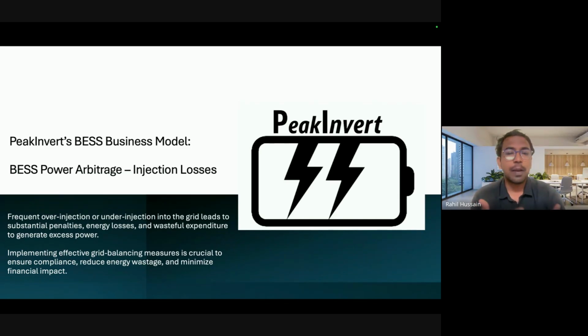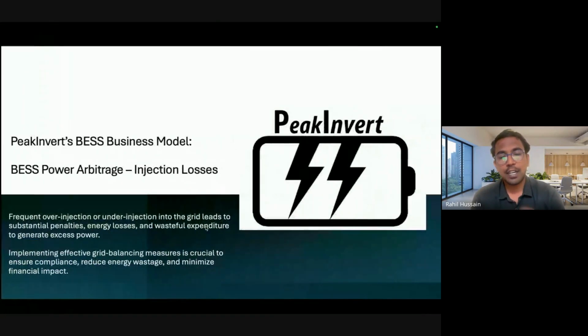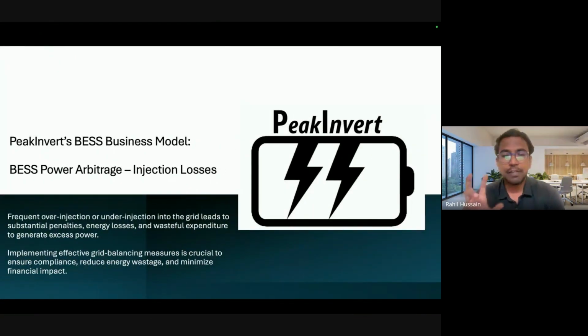When they are planning, they would have planned the inverter capacity to accommodate only part of the power being generated. So whatever extra power comes in, the inverter will clip that power and only take some part to transmit to the grid. So what we can do is, instead of pushing those clipping losses to the grid, we store them inside the battery, and reuse that whenever we are in need.